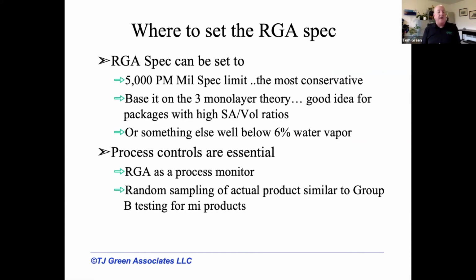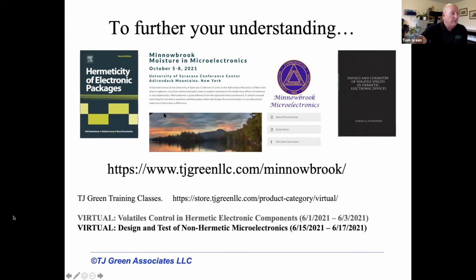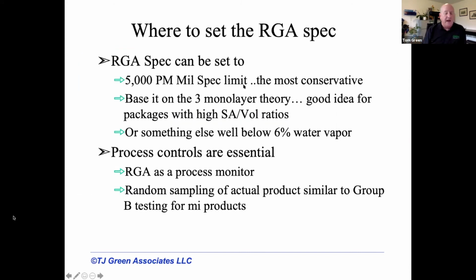All right, so where do we set that spec? Well, if you want to be conservative, if you want to state to your customers and to the FDA you're in full compliance with 1018, 5,000 parts per million is where you want to be. Now, if you have a battery, you're going to have to alter the test temperature. Or you could base it on the 3 monolayer theory. These two generally tend to be close to each other. Or maybe something higher than that, but still with plenty of margin, so you don't have any worries you're going to get anywhere close to 60,000 ppm, which means you basically have dew condensed out onto the part.